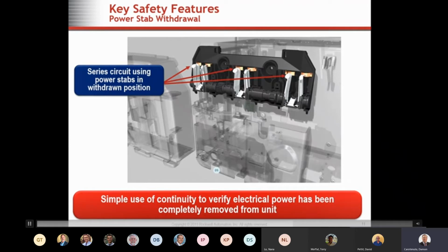They've all made contact with those devices, and you can get a complete circuit to help verify A, that the shutters are closed with the limit switch, and B, that the stabs are fully retracted through a continuity test. And that's one of the good things about that device on the front. You do not have to take the quarter turn device's word that these stabs are removed.